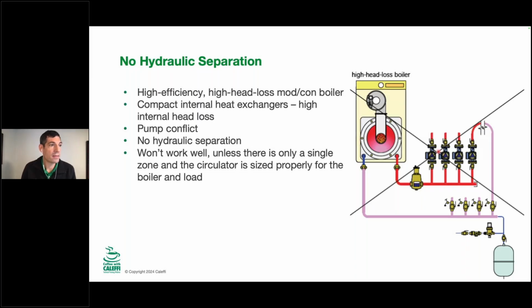So this scenario where we had maybe 1, 2, 3 of these circulators turn off and we just had one circulator going through a microzone was something that you were going to see 900,000 cycles in a year out of a ModCon in some of the mechanical rooms that I've been to over the years, which is very bad for everything. You're going to run through fan motors and gas valves and things like that because it's just really not what they're meant to do.